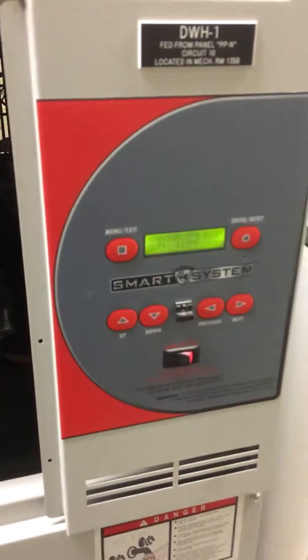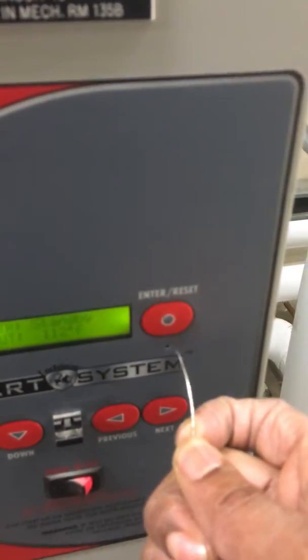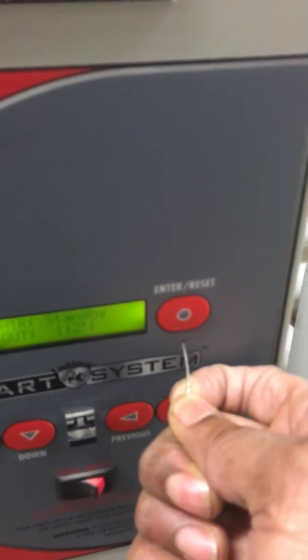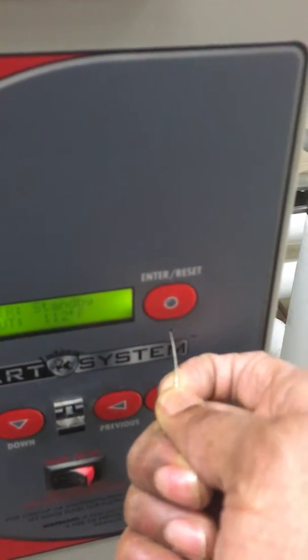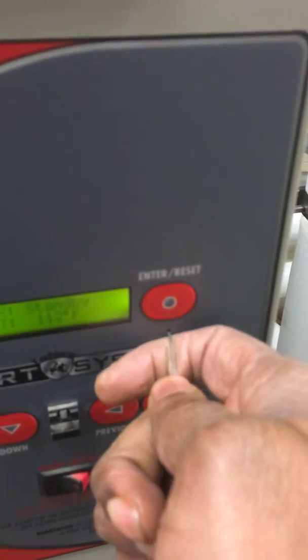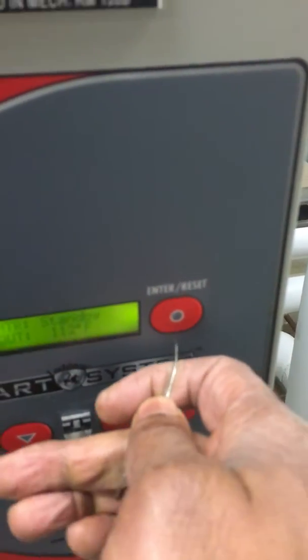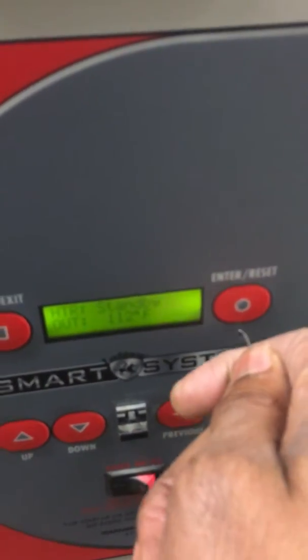So my next test is what I'm going to run is my high gas test. If you take a look, in the inside, that's my gas switch. See the switch here? This is my gas switch. So I'm going to turn that gas switch on. But once again, we have to set the Lochinvar water heater into service mode by sticking the instrument once again in the hole and holding it for a couple of seconds. And it will pop into service mode. And it will show that it's in service mode.